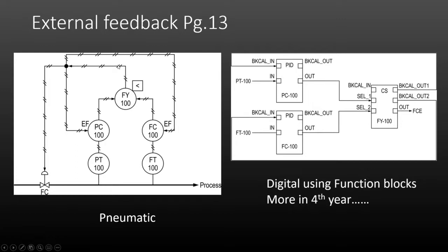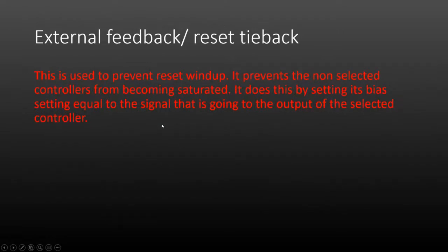With external feedback, the output from the selector goes to the control element and also to the non-selected controller. So if it's putting out 50% and the valve is half open, it sends the feedback signal to the selected controller at 50% and also sends the control signal to the non-selected controller at 50%. The external feedback or reset tieback is used to prevent reset windup.